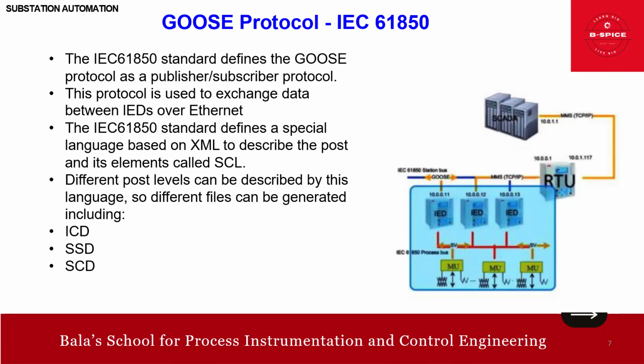GOOSE means Generic Object Oriented Substation Event protocol within the IEC 61850 standard. So what are the key points about the SCL? Standardized configuration: SCL provides a standardized way to describe the configuration of a substation automation system, including the communication between devices, which ensures interoperability between devices from different manufacturers. So that is standardized configuration. Then data set definition. In GOOSE messaging, friends, the SCL is used to define data sets that contain the status and values to be transmitted. These data sets are crucial for the proper functioning of GOOSE messages.